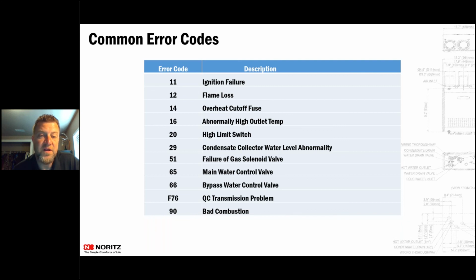With that ignition failure, make sure that your gas pressures are within parameters, because if it's over that pressure, so if you've got a natural gas unit and the maximum is 10.5 inches water column, and you've got 13, 14 inches water column, that unit will not light because the pressure is too high. So it could be wrong gas type, it could be the pressure's too high.